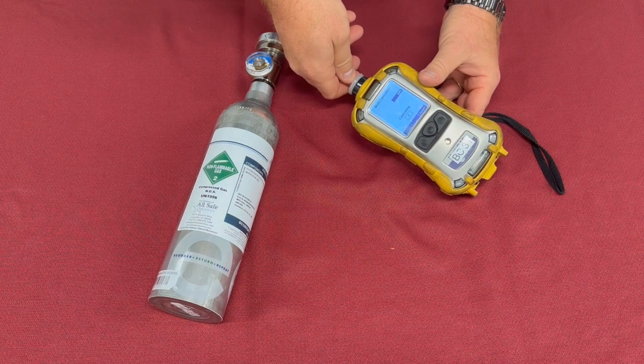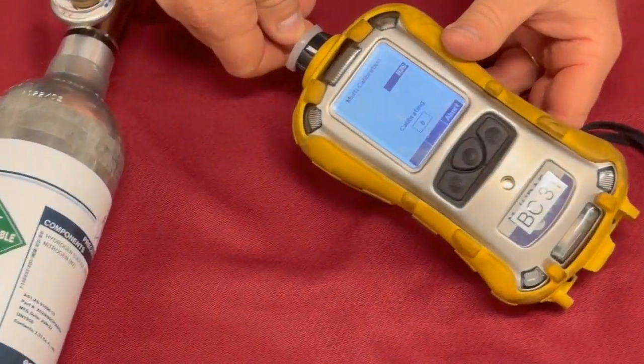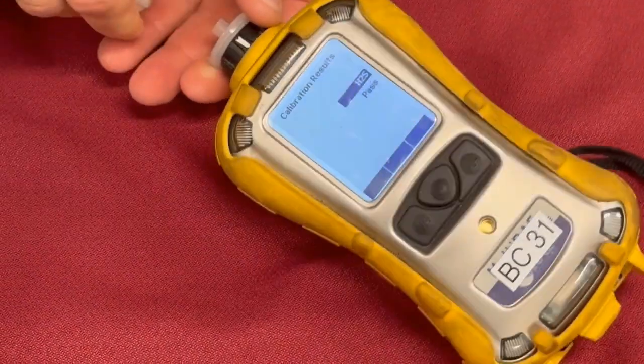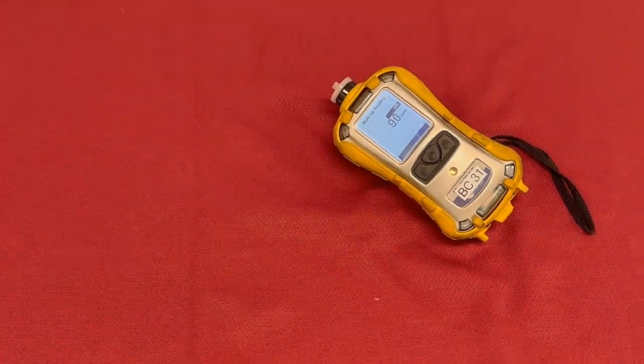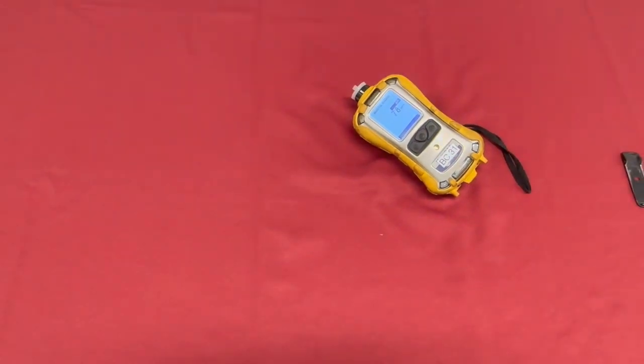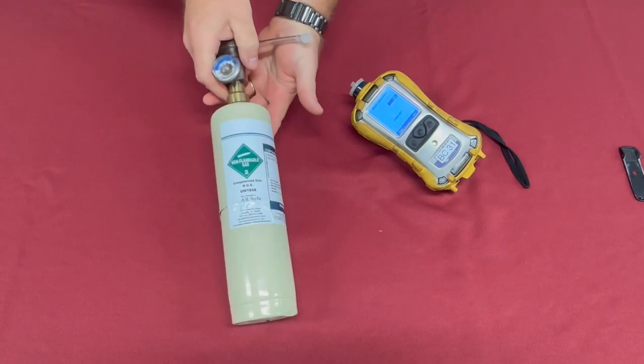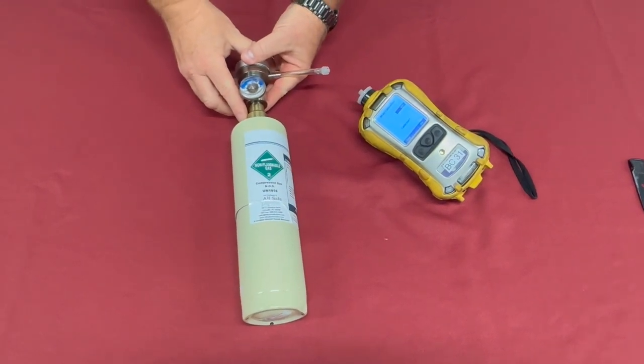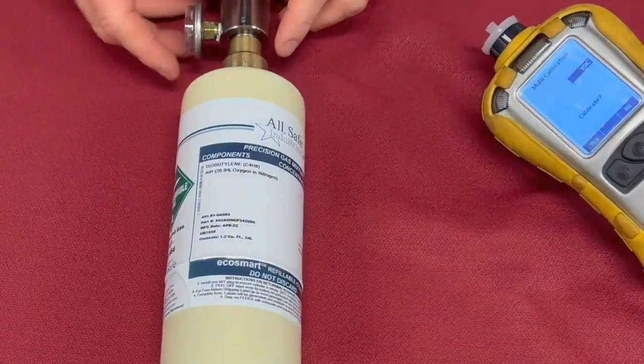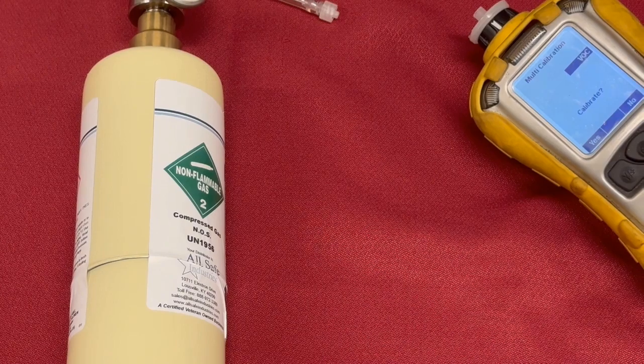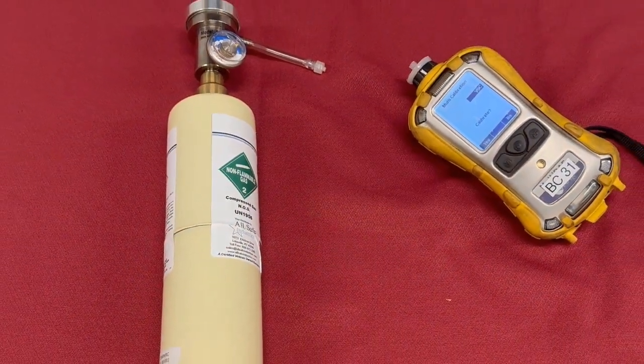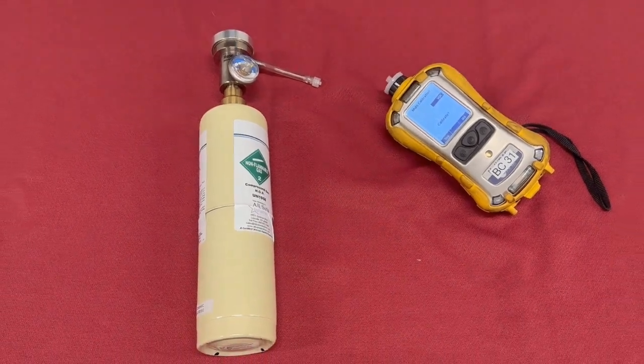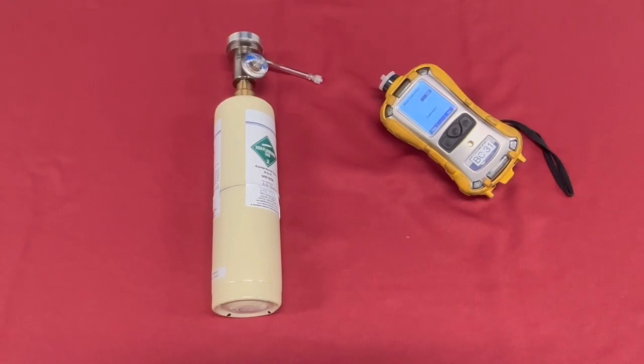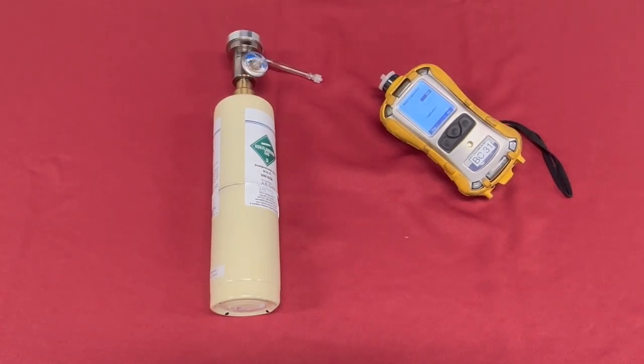All right, we'll see if this one passes. It passed. Okay, we'll give it just a moment to clear out while we get this cylinder ready. The cylinder of isobutylene uses the other gauge because it's a steel cylinder, and then you'll see it's labeled isobutylene. We use this to calibrate the PID, the photoionization detector. And it gets a little confusing because the PID actually shows up on your screen as VOC, volatile organic compounds. We'll very quickly talk about the operation of the meter here in just a moment. This is not an entire meter class, but we'll talk about individually the sensors and what your reaction should be here in just a moment.